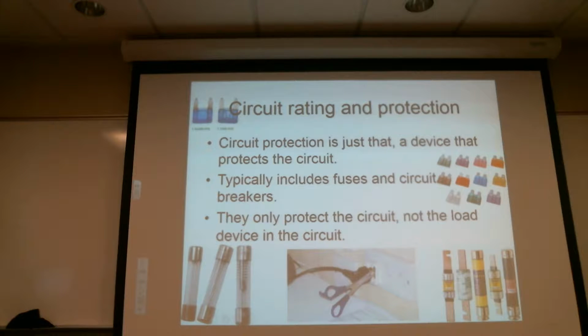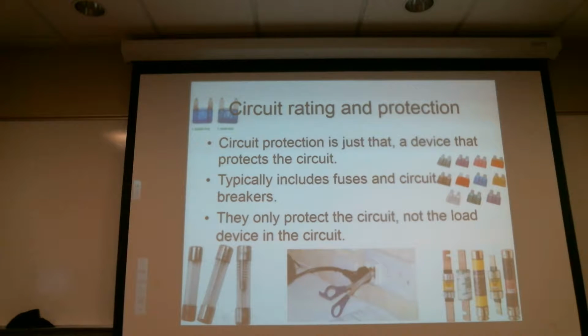If the circuit's designed correctly, the load will fail before the rest of the circuit will. Right? And it'll stop conducting current. It'll fry, it'll short, it'll one way or another stop working. The real goal of circuit protection is if something damages the circuit itself. Now, is it possible for a load to internally somehow fail and overload the rest of the circuit? Yes, it's possible, in which case the fuse would blow or the circuit breaker would blow anyways. And at that point, the load's toast because that's what fried everything in the first place.